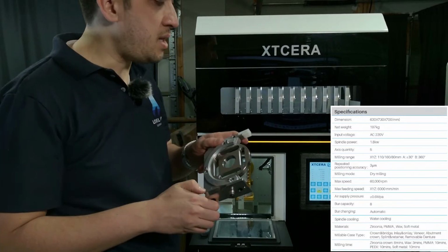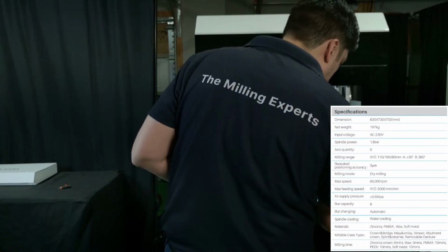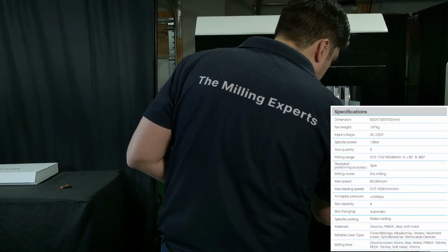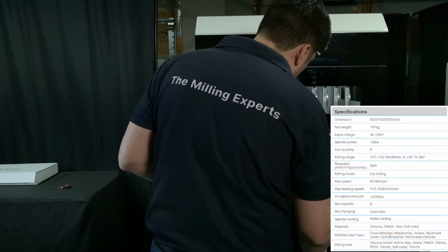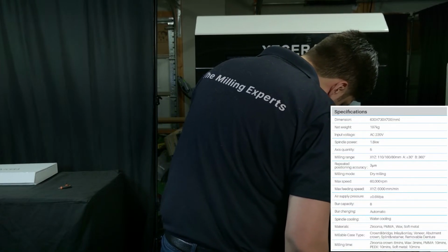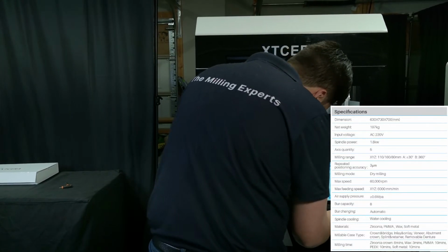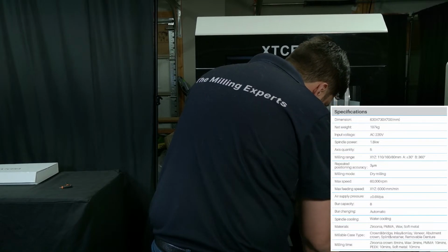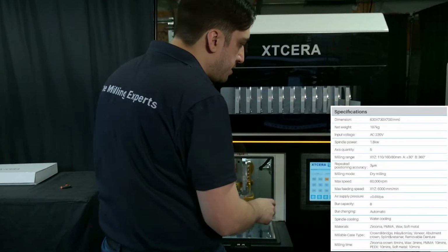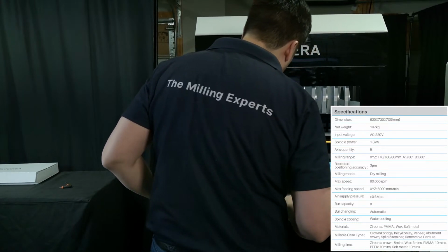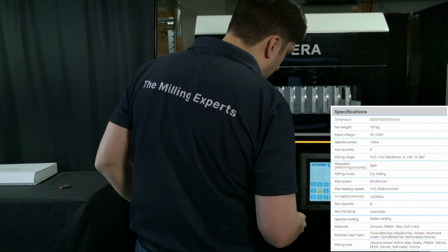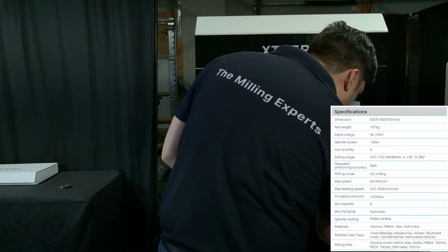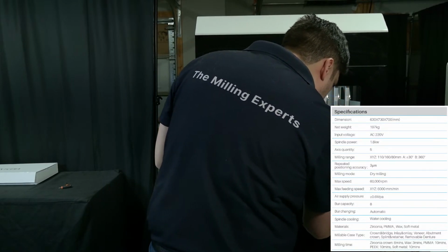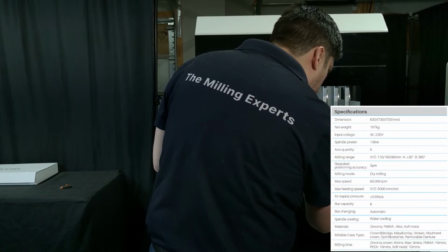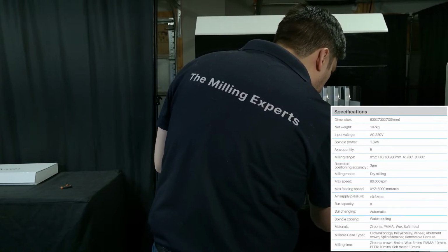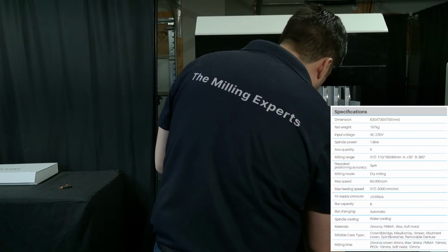Next up, I've got my calibration jig mounted inside of one of my adapters. Now I'm just going to go to my adapter control, open up my chuck. All right, make sure that's in there, nice and indexed. Chuck is now holding it securely in place. So at this point, everything is ready for the calibration process to start. I guess I could probably leave this open here. We're going to go and click on calibrate. It's saying learning instructions of this function. Be sure to calibrate the disc holder. Yes, we want to calibrate it.